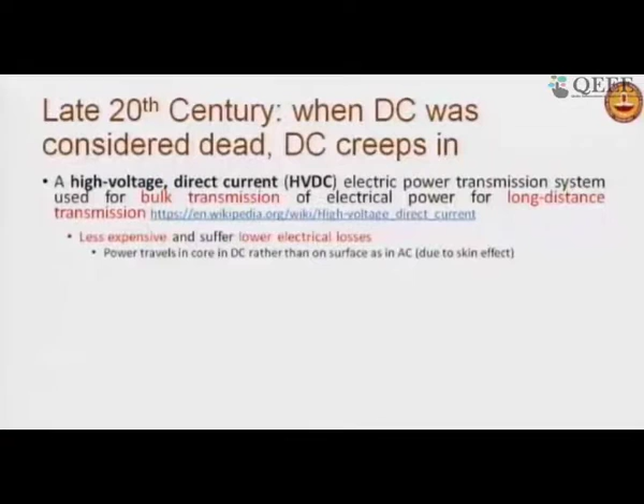Similarly, for underwater power cables, DC avoids the heavy currents needed to charge and discharge the cable's capacitance each cycle, 50 times every second at 50 hertz, since water is a poor conductor but not a zero conductor. Even for the shortest distances, the higher cost of DC conversion equipment may still be warranted by the benefits of direct current.